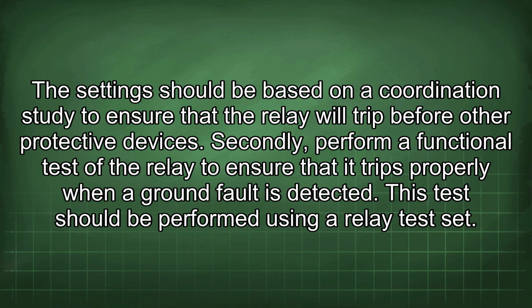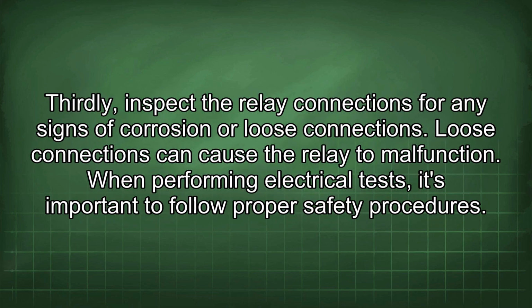Secondly, perform a functional test of the relay to ensure that it trips properly when a ground fault is detected. This test should be performed using a relay test set. Thirdly, inspect the relay connections for any signs of corrosion or loose connections. Loose connections can cause the relay to malfunction.